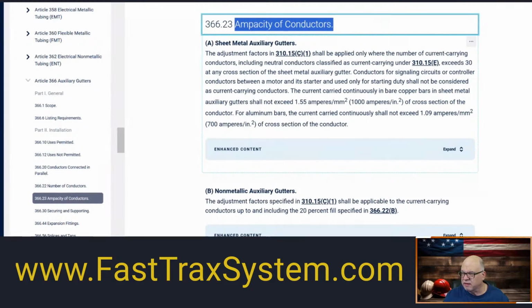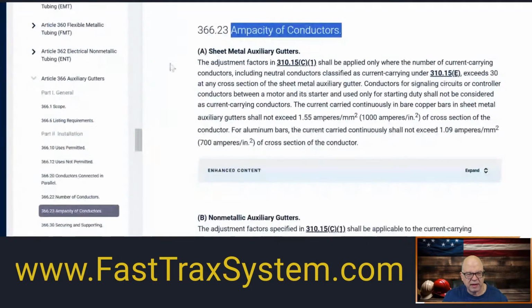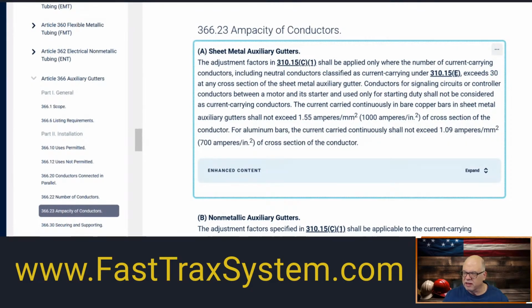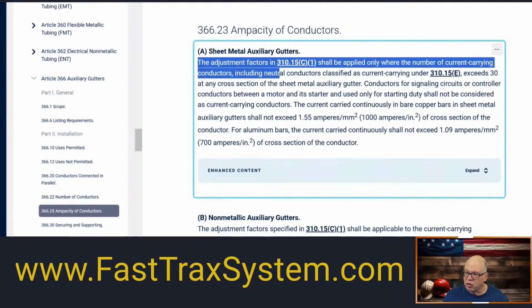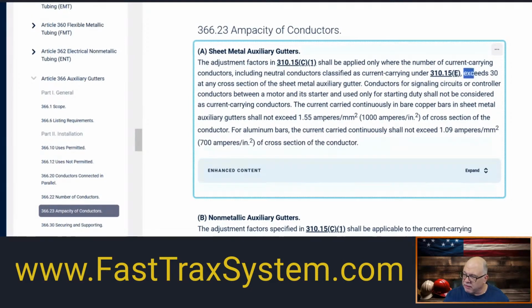So as I'm looking at this and just staring at it, I'm also noticing that it is including a reference. So I remember that reference right here. Let me see if I can blow this up a little bit for you. I know it's sometimes tough to see. Right here, reference. And I also see a 30 in here, which was one of our answers. Okay, so the adjustment factors in 310.15(C)(1) shall be applied only where the number of current carrying conductors, including those neutrals that are classified as current carrying. And remember, in a 2-wire circuit, that neutral is a current carrying conductor. Most normal branch circuits, the neutral is a current carrying conductor, normal application. So if it exceeds 30 at any cross-sectional area of the sheet metal gutter, that type of thing.